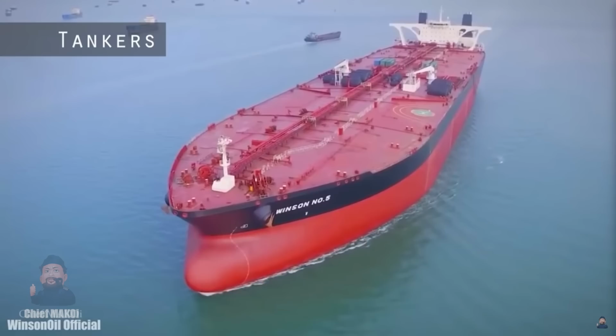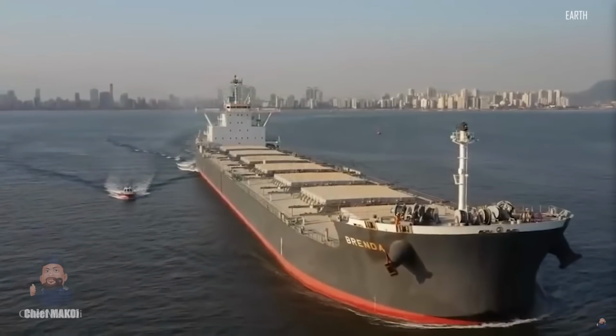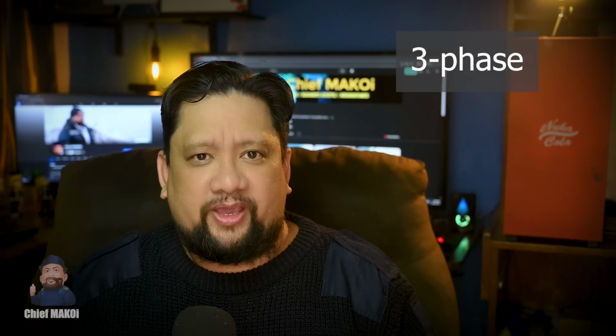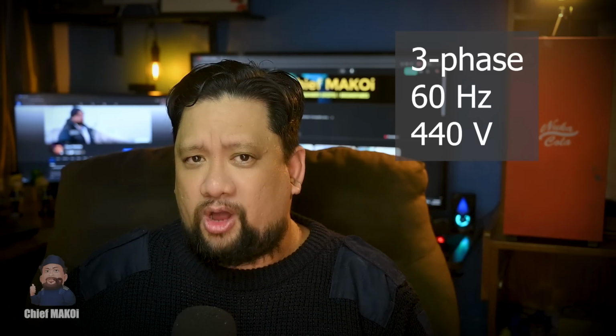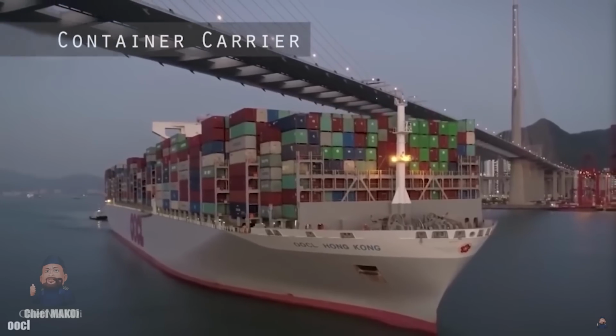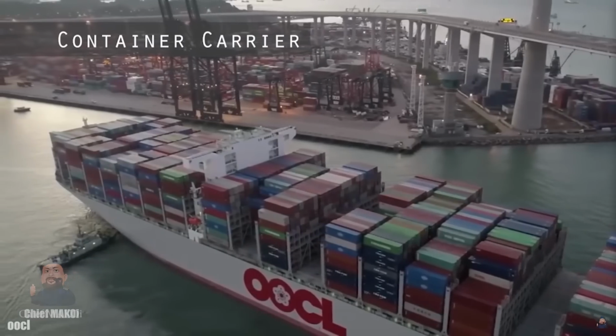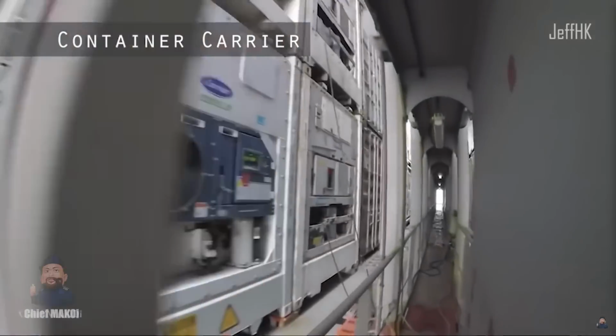First up, let's clarify some things about container ships and their differences in electrical requirements compared to other cargo ships. Other types of cargo ships like tankers and bulk carriers don't generate high voltage electricity. They typically generate three-phase 60 Hz 440 volt supply, which is used to operate the various machinery on board. This means there's no high voltage bus. The generators produce only 440 volts and directly connect to the 440 volt bus. On the other hand, ships that require a huge amount of electrical power have a high voltage system. This is typical for container ships, and in the case of Dali, which has 1,400 slots for reefer or refrigerated containers, it requires around 8,000 kilowatts of additional power in case all of those slots are used.